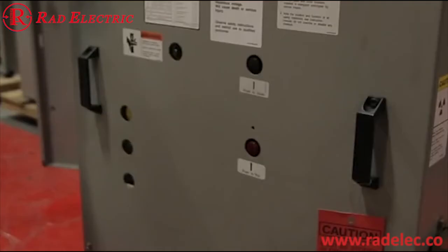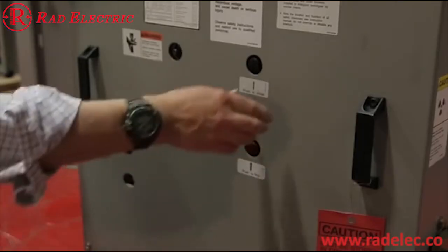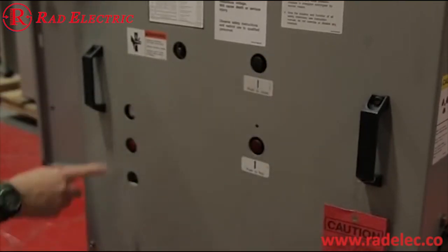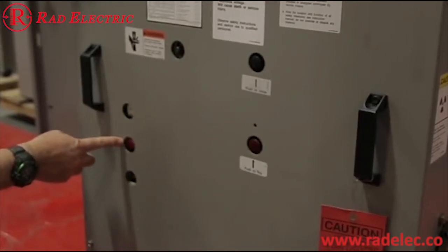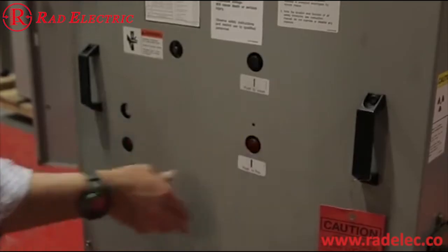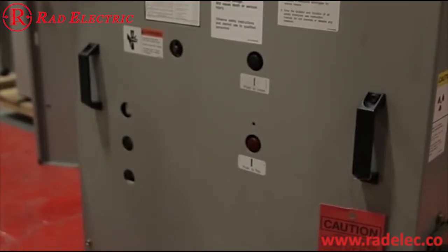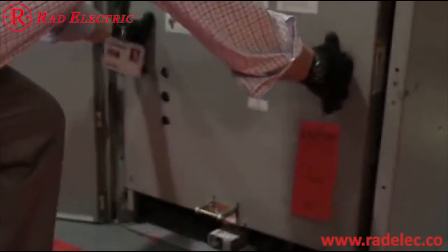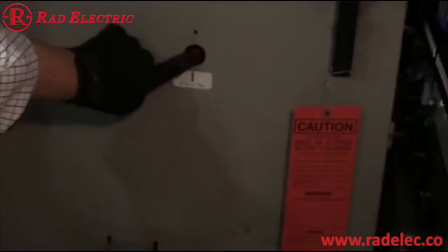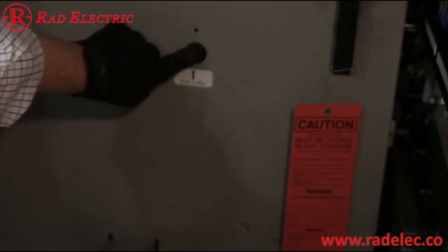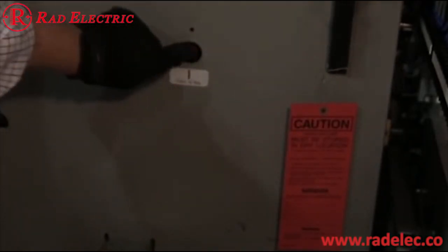Next, we're going to demonstrate the spring discharge check procedure. Perform the spring discharge check before removing the circuit breaker from the pallet or switchgear. The spring discharge check should be performed after de-energizing control power. This check assures both the tripping and closing springs are fully discharged. Open the circuit breaker and rack to the disconnect position, and then perform the spring discharge check. Press the red trip push button, and then press the black close push button. Press the red trip push button again. Verify the spring condition indicator shows discharged, and then verify that the main contact status indicator shows open.